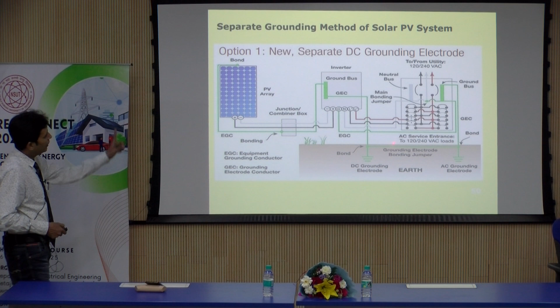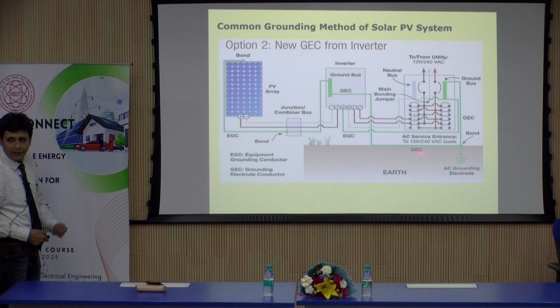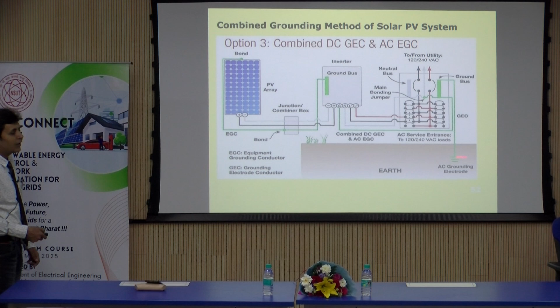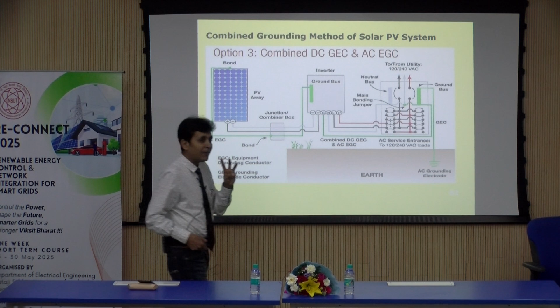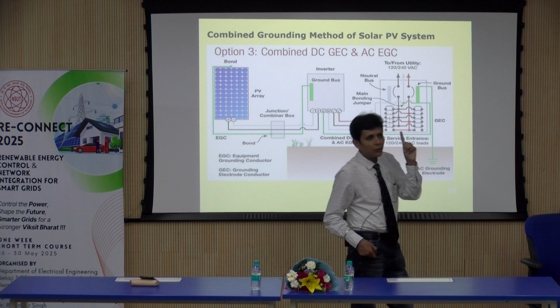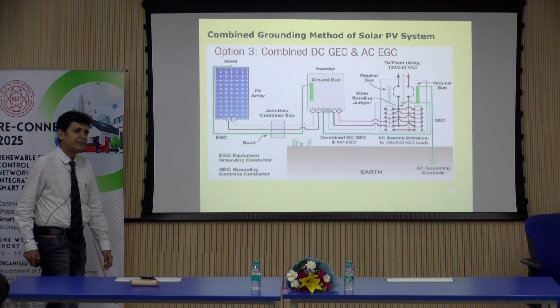Option number 2, next one. What you do, you take the GEC from the inverter itself. The grounding electrode conductor you are taking from this one. There is no separate electrode system for both. Third, this is a combined system where only one electrode is required. But in the Indian system, it is mandatory as per the government MNRE guidelines to have 3 electrodes. One is for your lightning, one is for your equipment, one is for inverter systems. So we have to connect all of them. Yeah, I am coming to that one.